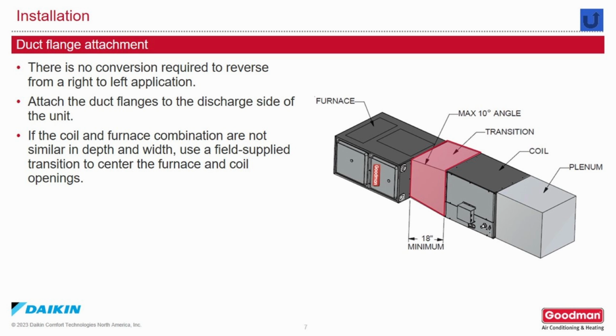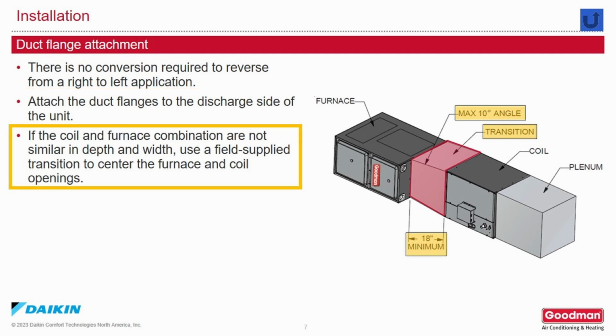For the duct flange attachments, there are no conversions required to reverse from a right to a left-hand horizontal application. Apply the duct flanges to the discharge side of the unit. If the case coil and the furnace are not the same in depth or width, use a field-supplied transition to the center of the furnace and coil openings.